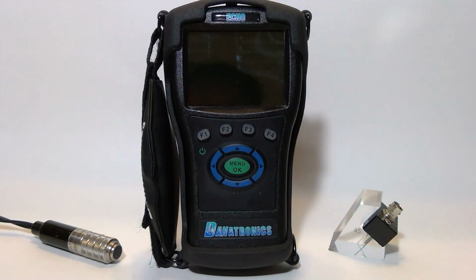The FD is capable of performing most everyday flaw detection needs like weld inspection and corrosion scanning, to name a few. It comes standard with software features such as AWS D1.1, DAC, B-Scan, phase change detection with alarm, and also has a 2 GB expandable to 32 GB micro SD data logger. It can also store 2,700 unique transducer and application setups.